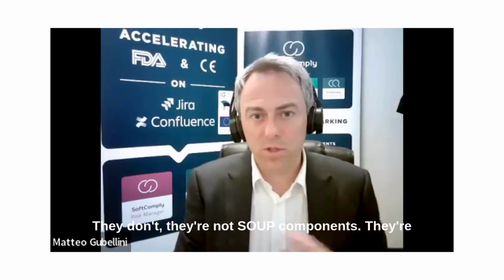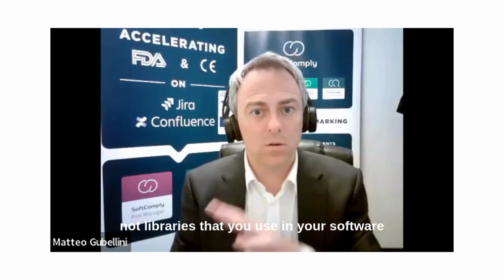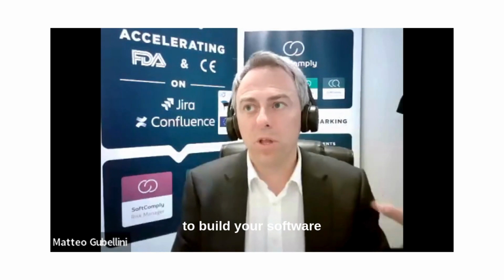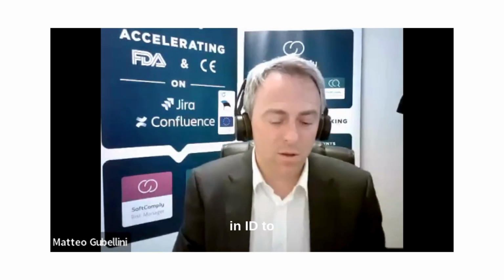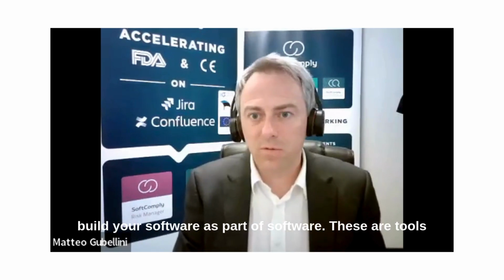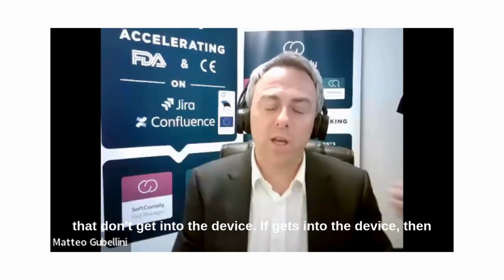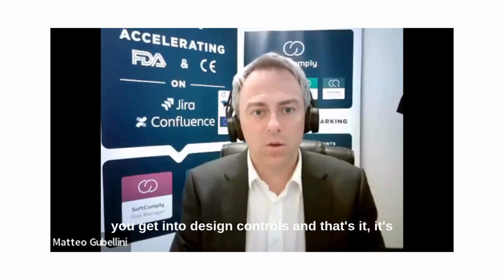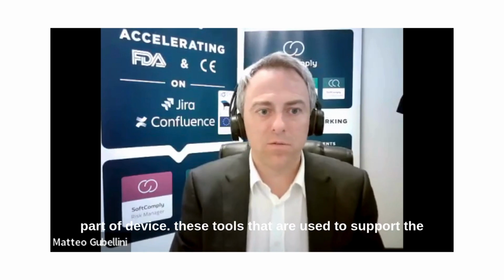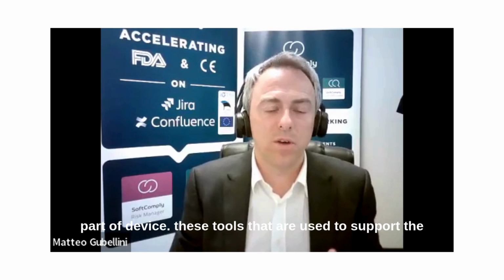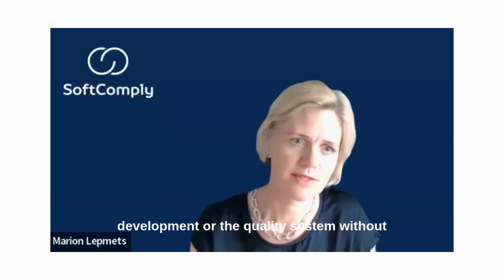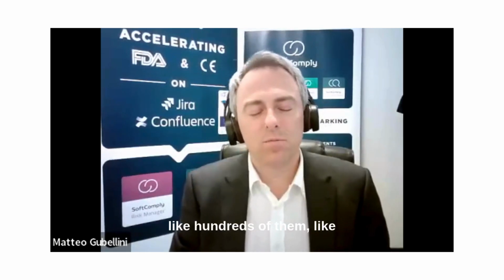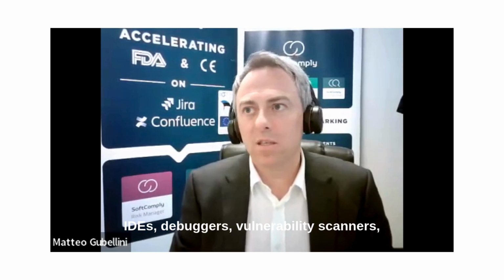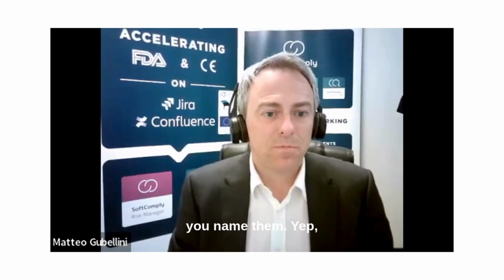They're not SOUP components. They're not libraries that you use in your software, or the IDE to build your software as part of the software. These are tools that don't get into the device. If it gets into the device, then you get into design controls, and that's it. It's part of the device. But these are tools that are used to support the development or the quality system, like Confluence, Jira, like hundreds of them, like IDEs, debuggers, vulnerability scanners, you name them.